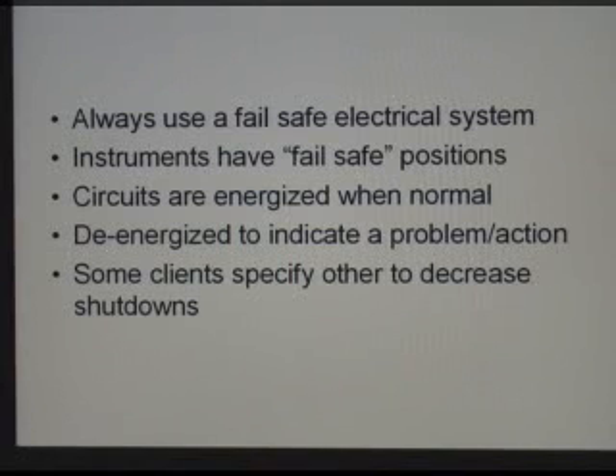And in that way, if we have a positive signal when something is normal, and we take away that signal, that means that if for some reason we should ever have a wire break or a wire come off of a terminal, we'll end up shutting the machine down, rather than having a shutdown protection device no longer functioning if we had an energized-to-indicate-a-problem system.